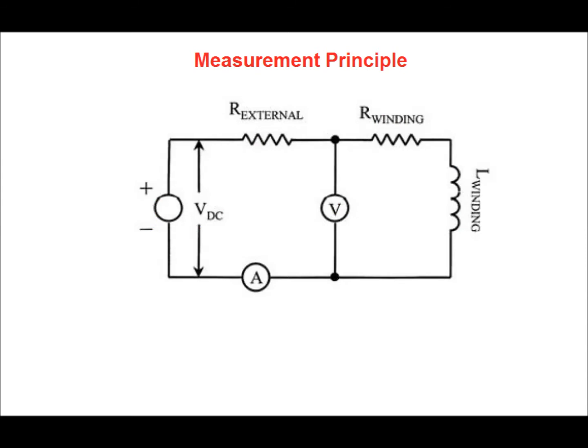DC resistance test principle. The diagram shown is for measurement of the DC resistance test. Here, a DC test current is injected across the measured winding, and the voltage drop as well as the test current is measured, and the resistance is calculated by Ohm's law, that is V drop by I injected.